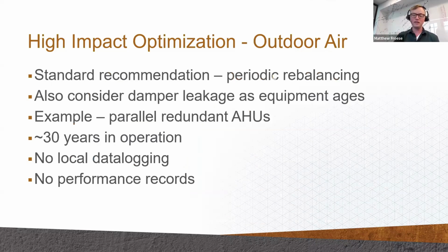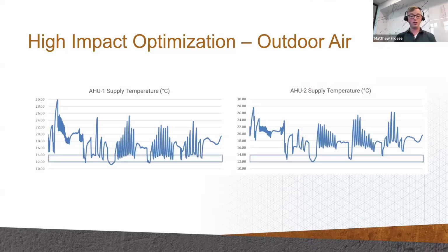So outdoor air, we also see a lot of drift, I think. Standard recommendation is periodic rebalancing, which I'm quite sure almost nobody does. We see a lot of damper leakage and breakdown in equipment over time. So this is just a quick example of a case where we had an existing building with parallel redundant air handlers and no local control. Nope, not even any original performance records. But what we were able to do with just some local data logging is take a look at supply temperatures between two systems that we knew were having some problems.